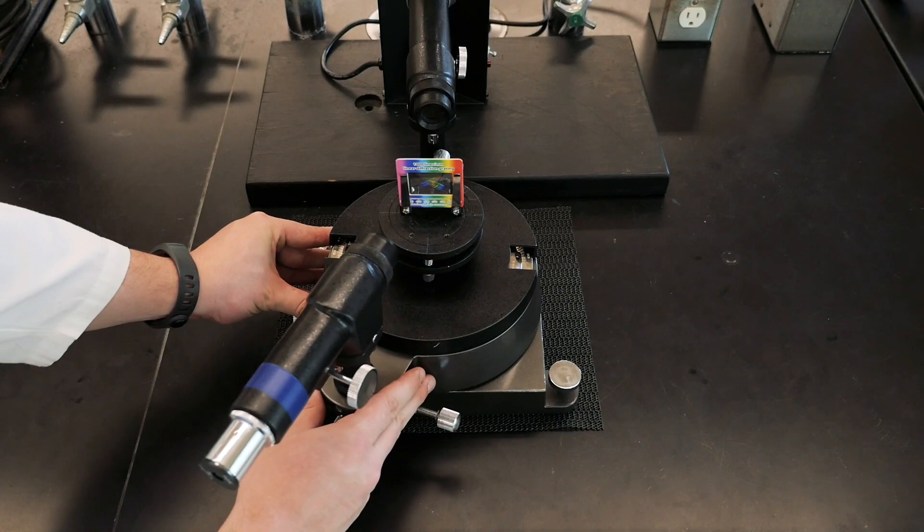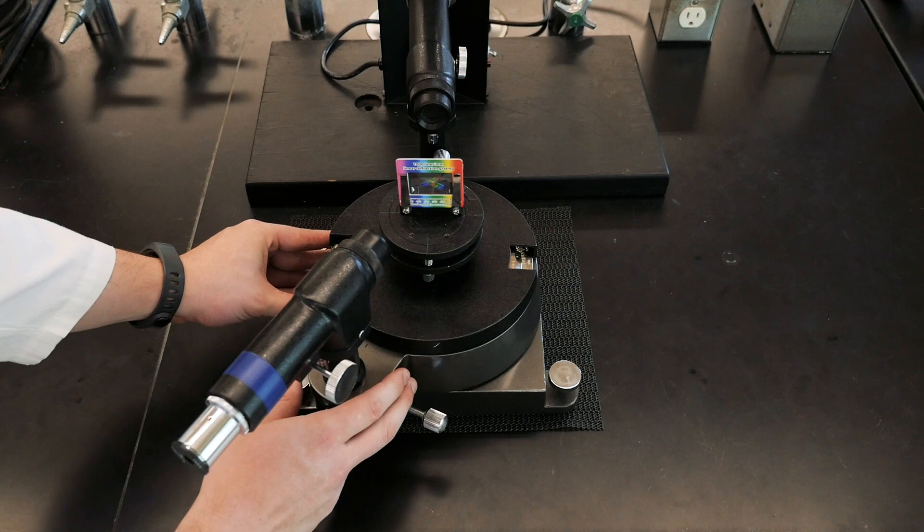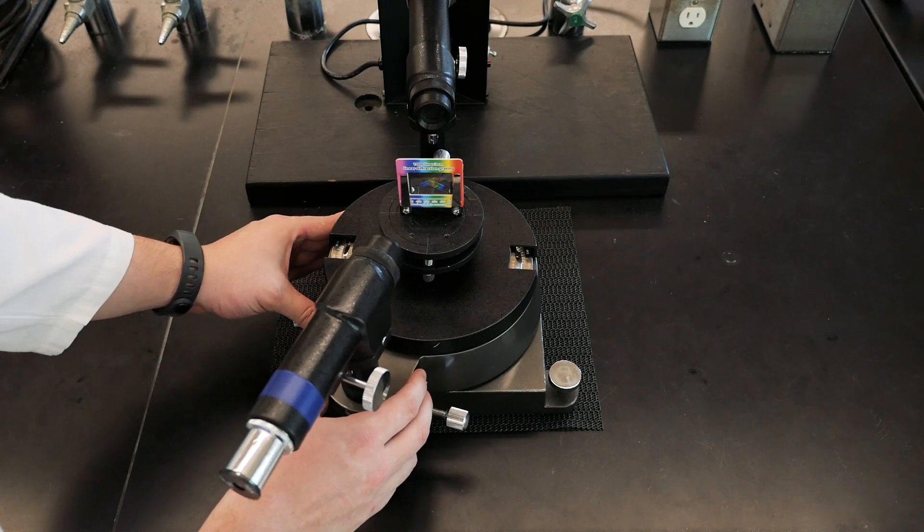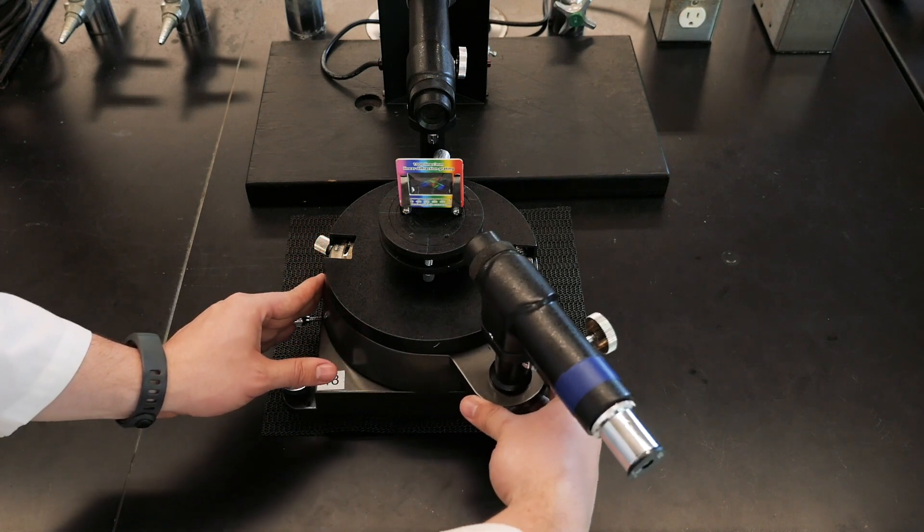if you rotate it in the opposite direction, say five degrees, then the gauge will be reading five degrees past zero in the opposite direction, which will actually be 355 degrees, since zero is actually the same as 360 degrees of a full turn. So when going in this direction, be sure to subtract your reading from 360 to get the true angle of diffraction. Once you've measured the diffraction angles in both the clockwise and counterclockwise directions, simply average them to arrive at your final measurement.